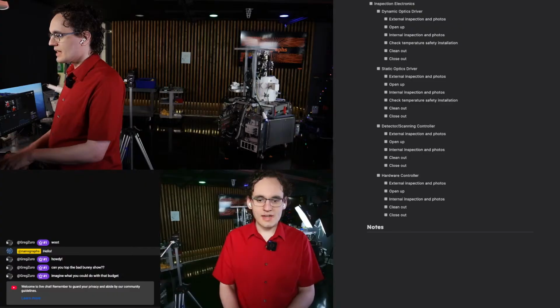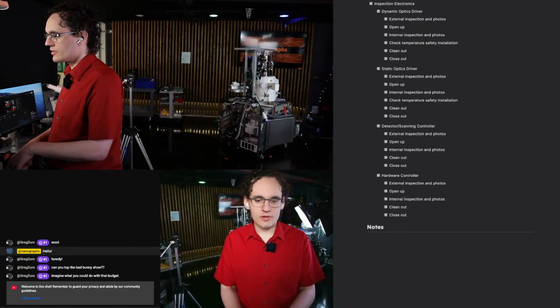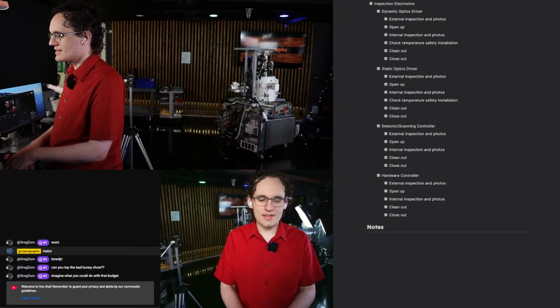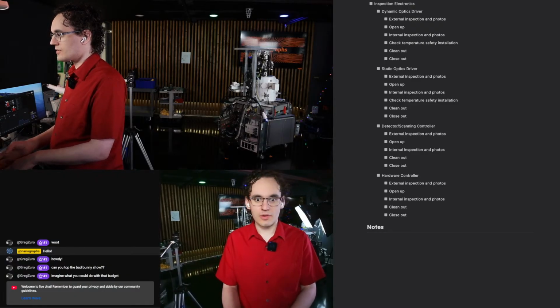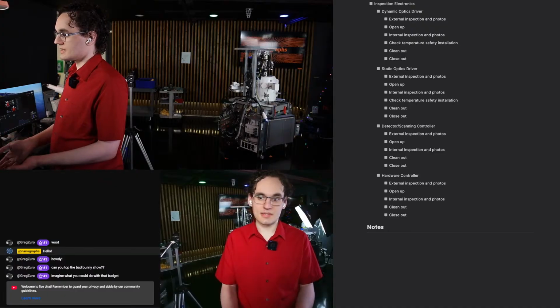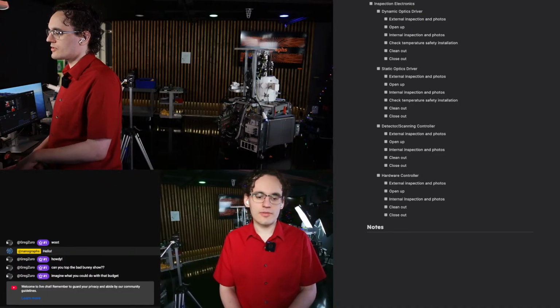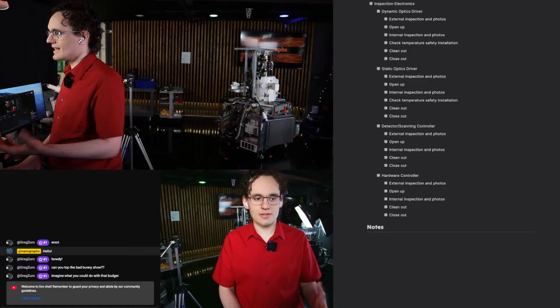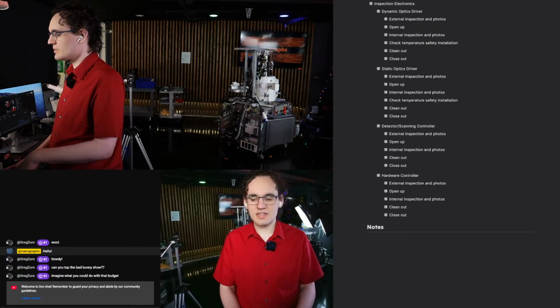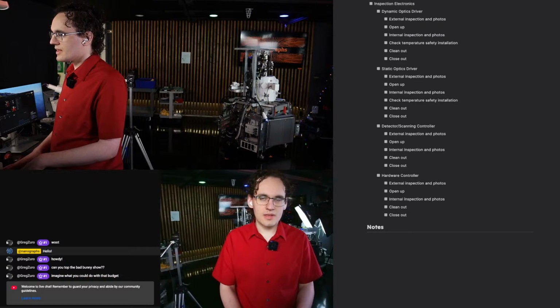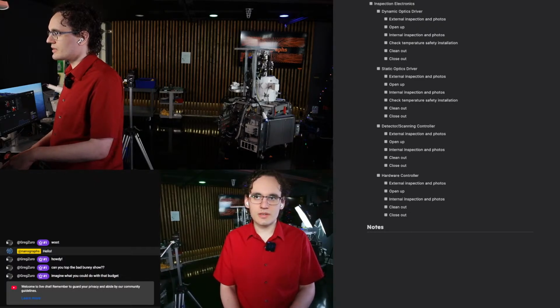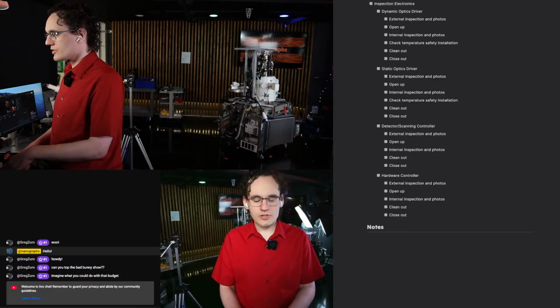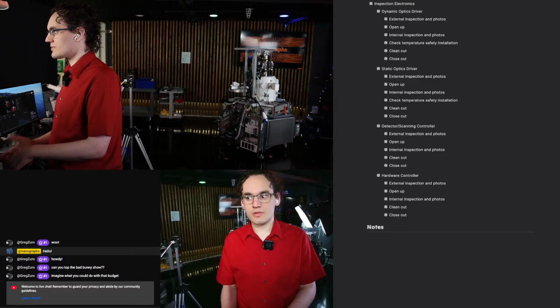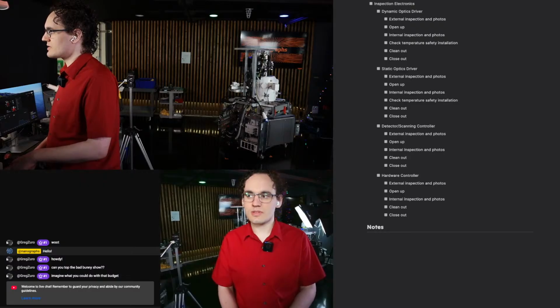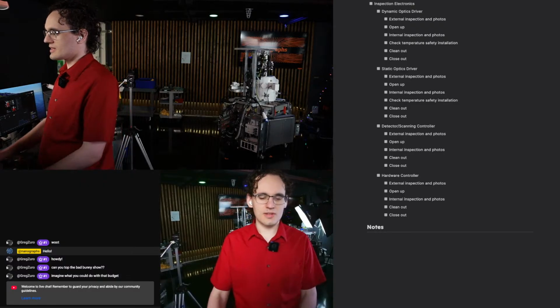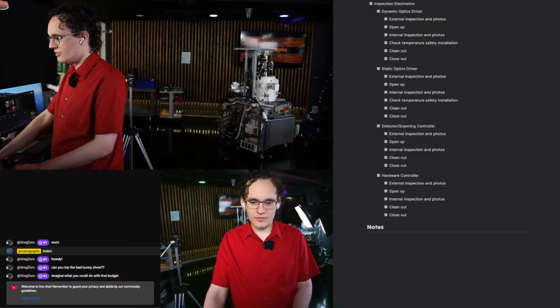I'm probably not going to get to all of this tonight, but this is what we're working on. So, dynamic optics driver, static optics driver. It's not really static, but it's referred to as that. The dynamic optics are our scan coils, right? They're moving very quickly, constantly, because it's a scanning electron microscope. The static optics drivers are like the objective lens, condenser lens, and stigmator. Source alignment coils are technically a dynamic optic driver, but they're actually really slow. It does actually scan the source alignment coils, which is kind of interesting, but it does so really slowly, using much lower speed electronics. So it's considered a static optic that can move quickly.